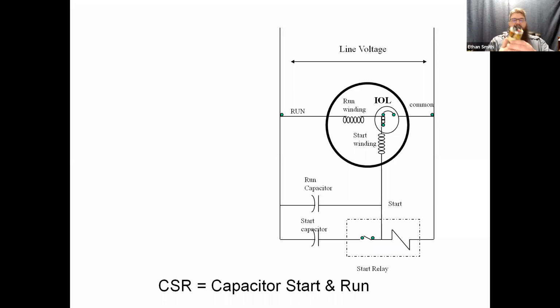So you'll have a start relay that'll have a 330 volt pickup voltage. And the reason is they're using the back EMF of that motor to pull that start relay in once the motor is spinning. Okay. And so what we're doing is we've got a capacitor in series with the start winding, just like our PSC motor, for efficiency. And then we've got a start capacitor in series or in parallel with the start winding for starting torque. So now we don't necessarily have to balance efficiency versus torque, because we can give it a whole bunch of torque until it starts moving and then drop it out and then have another capacitor there that's just for efficiency.